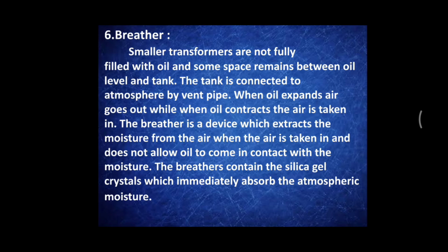The breather is a device which extracts the moisture from the air when the air is taken in, and does not allow the oil to come in contact with the moisture. The breather contains silica gel crystals which immediately absorb the atmospheric moisture.